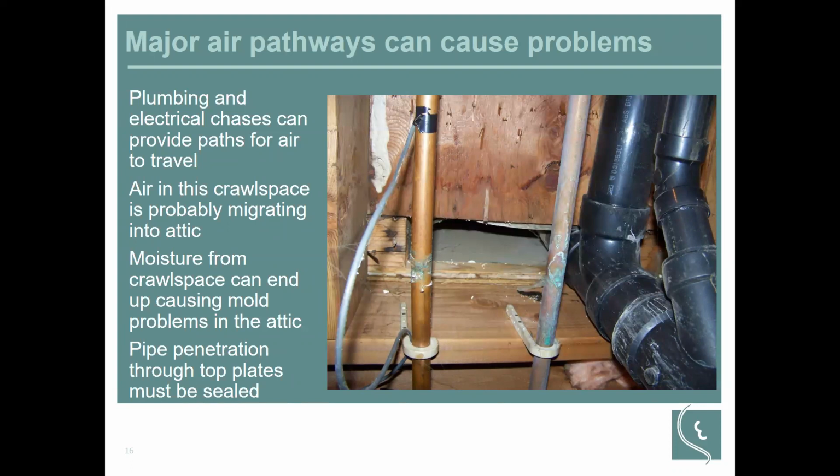That air is humid. That humid air, as it warms up, travels up these chases and goes through penetrations through the top plate where that plumbing stack goes through and creates problems in the attic. We have been in several attics where moisture from the crawl space has migrated up into the attic and caused all kinds of mold problems. And the moisture came from the crawl space. It was not from leaks from the roof or anything like that. So these types of chases need to be sealed.